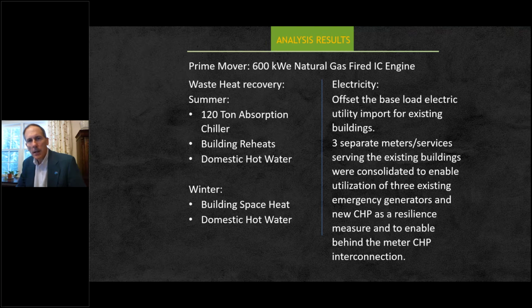Regarding the electric side, the system was designed to offset the base load electric utility import for the existing buildings. 3 separate meters and services serving the existing buildings were consolidated into one primary service to enable utilization of the 3 existing emergency generators and the new CHP as a resilience measure, and to enable behind-the-meter CHP interconnection. An added bonus in terms of savings was that 2 of the buildings' meters were secondary service, and by switching them over to primary, there was also a savings.